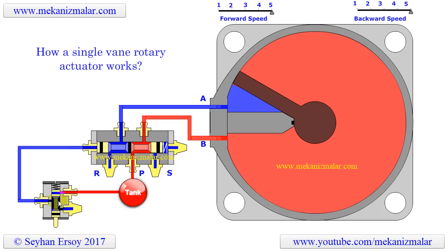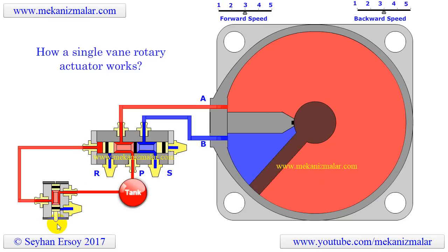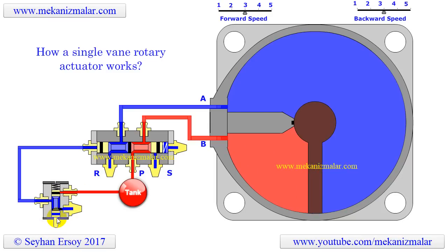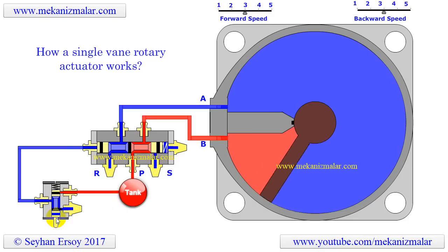While rotary actuators can be manufactured for both hydraulic and pneumatic applications, there are some differences in their behavior. The pneumatic rotary actuator moves from one end of the circular reciprocation to the other very rapidly, making it harder to control its position. It is also harder to hold the pneumatic rotary actuator at a certain angle due to the expansion ability of air.